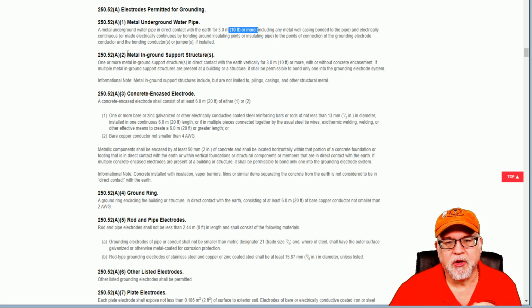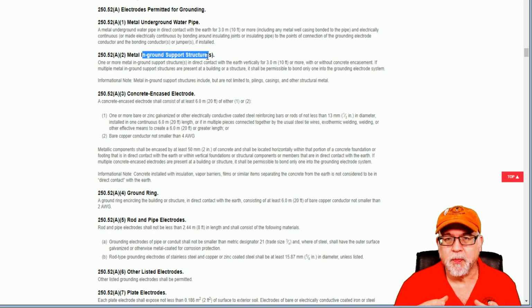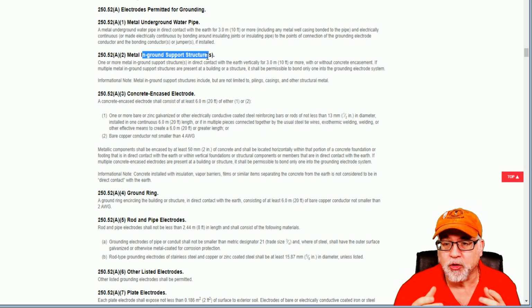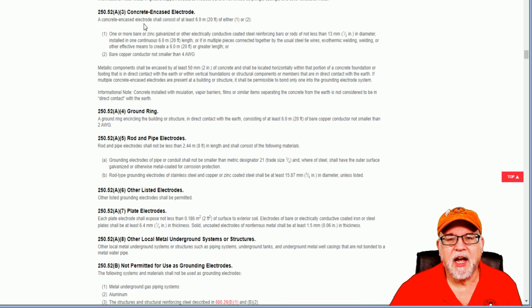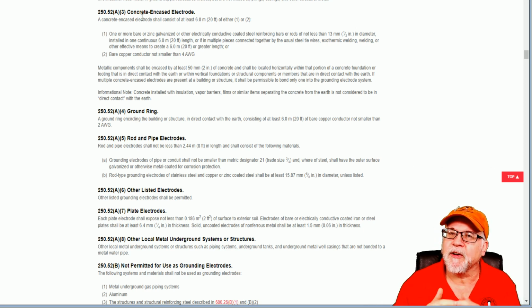And then, of course, you have what's called (A)(2), which is a metal in-ground support structure. You've probably seen metal support like I-beam steel that's driven into the earth, or encased in concrete, but it's 10 feet or more, either encased in concrete or in direct contact with the earth, and that would qualify as a grounding electrode. Of course, you have concrete encased electrodes, which is basically rebar inside of concrete, which is in contact with the earth. So the rebar is in the concrete, and then the concrete is in contact with the earth. And again, that is very common in construction.